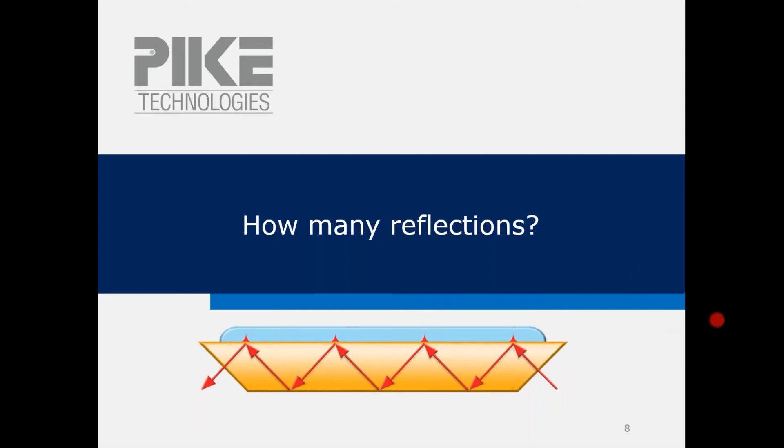That really depends on how someone's defining it. I've seen commercial manufacturers define it both ways. Most often at Pike, we define it as the number of reflections on the sample. So in our case, we would call this four reflections. So this is important when you're working on publications. It's always important to understand the dimensions of your multiple reflection ATR element. So if you read in a publication, oh, they used a 10 reflection crystal, well, is that 10 reflections on the sample or is it 10 total reflections?